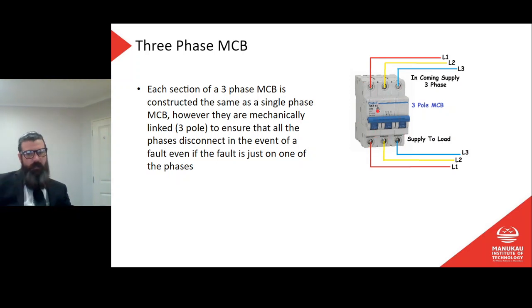Just think of it as three separate breakers, and then that handle there, or what do you call that? Somebody watching this video, send me a text and tell me what you call that. The little thingy there is constructed so it's joined together, so you can't switch one without the other. So if circuit breaker number one trips because it has an overload, then as it moves, it's going to pull these other two down with it and switch off.